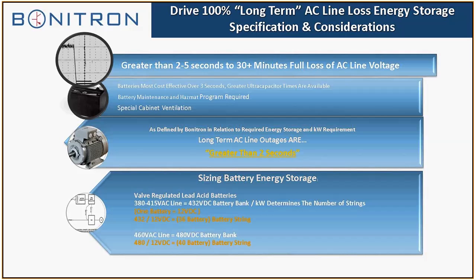Sizing battery energy storage: the battery bank has to maintain a certain voltage to be able to boost into the DC bus of the drive. Remember, it's a 2-to-1 booster, so we don't have to have the full DC bus voltage. A couple of examples of line voltages in correlation to battery banks. A 380 volt to 415 volt AC line is going to be a 432 volt DC battery bank. That translates to basically 36 12-volt batteries in a string. Usually when we specify batteries, we look at the kilowatts, the time, and what the DC bus battery bank has to maintain to be used with the ride-through booster. A 460 volt line would be a 480 volt DC battery bank, which is 40 12-volt batteries in a battery string.